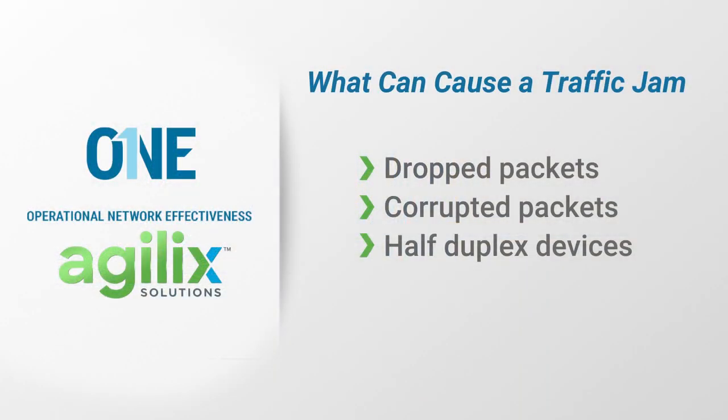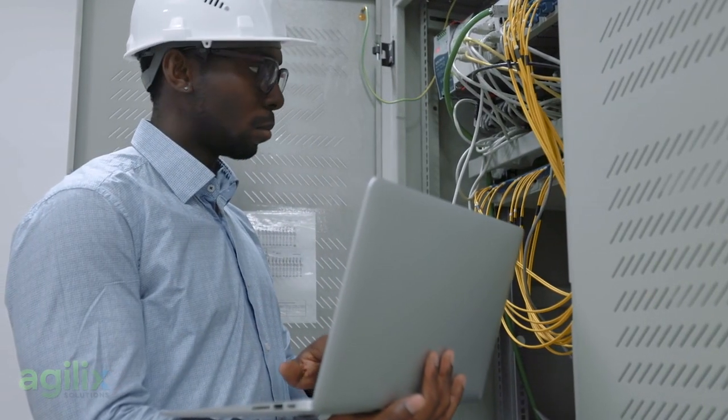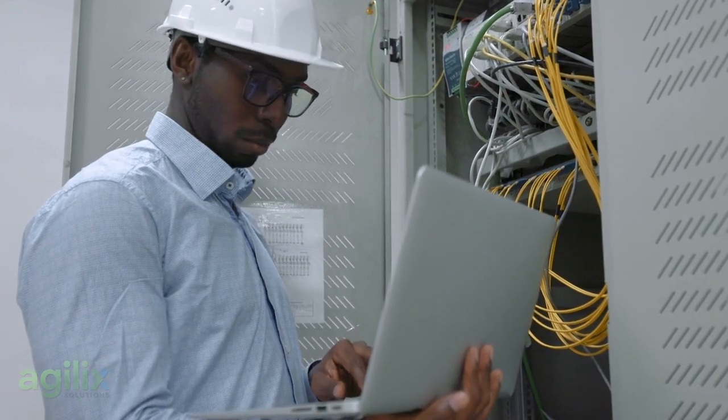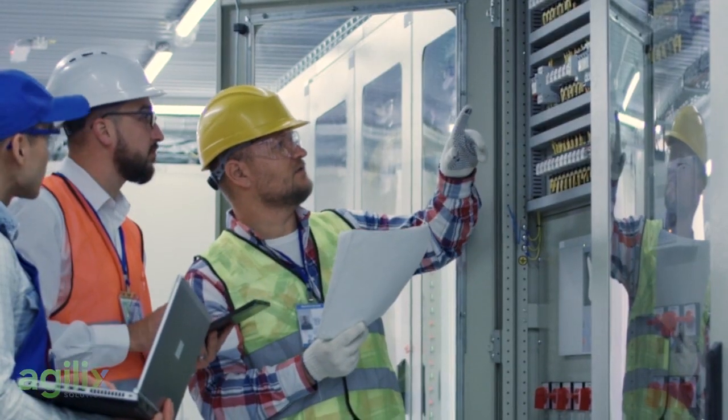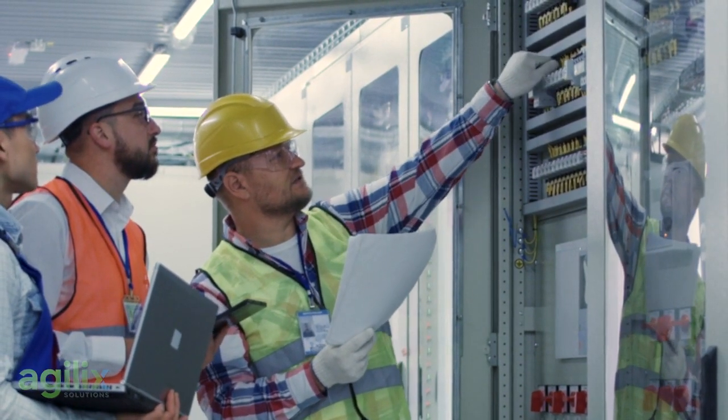There's another item that can cause or contribute to traffic jams, and that's what I call old logic in a process. So as our process evolves with time, some devices get added, some of them get deleted. But if we don't update the process logic for deleted items, the processor or the PLC is constantly trying to establish communications to that device that's no longer present. It's called an ARP. ARP traffic is just an added data flow onto our already constrained pipe.